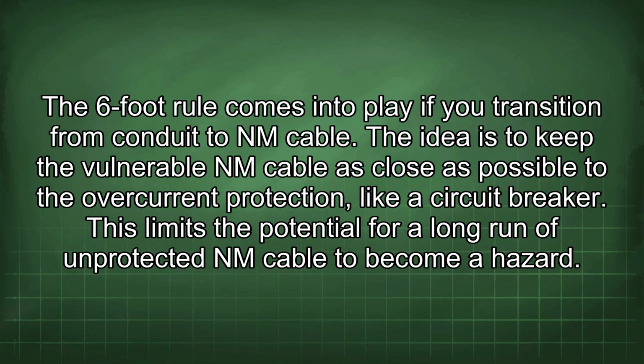The 6-foot rule comes into play if you transition from conduit to NM cable. The idea is to keep the vulnerable NM cable as close as possible to the overcurrent protection, like a circuit breaker. This limits the potential for a long run of unprotected NM cable to become a hazard.